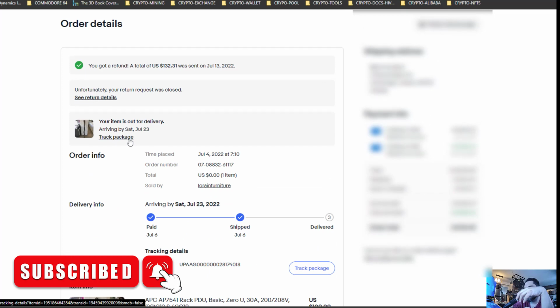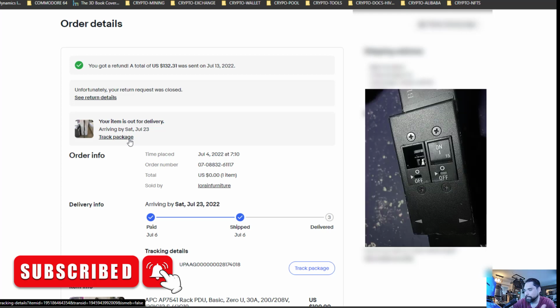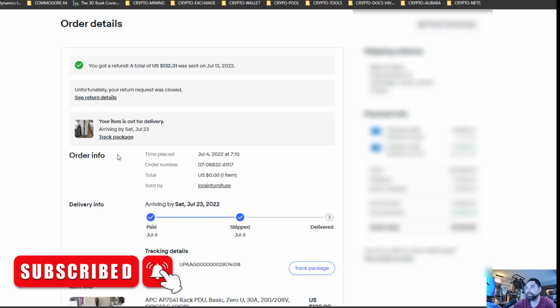I took apart the unit where the breakers are on the actual PDU. One of the wires wasn't even connected, and it was bubbling up from inside, turning brown - it just wasn't working at all. Not only that, but the actual switch mechanism that flips when the breaker switches on the PDU was completely broken, and one was completely missing.